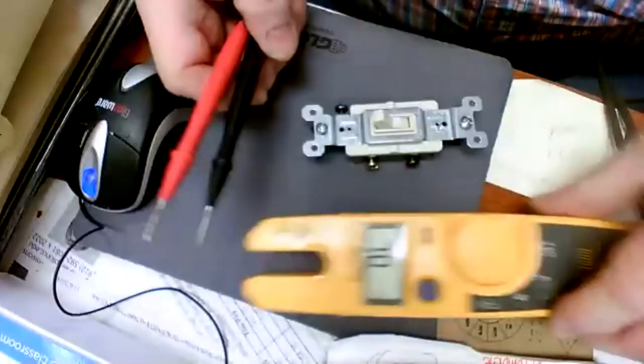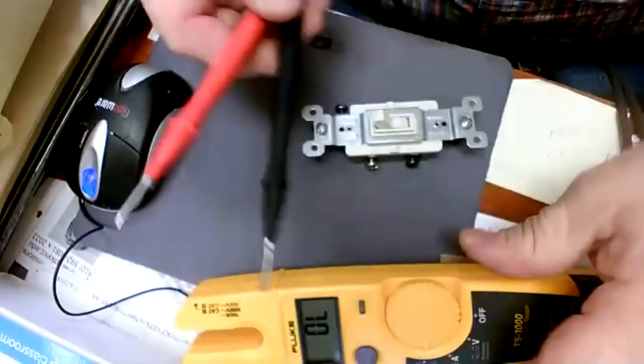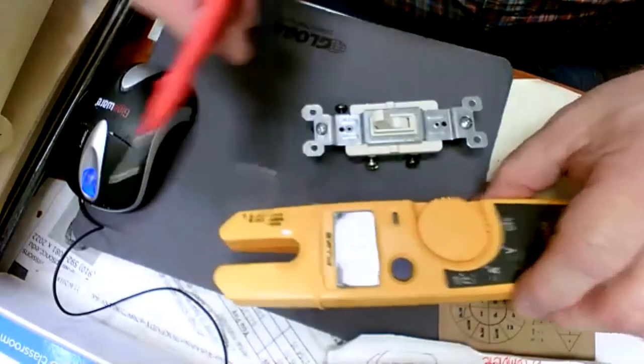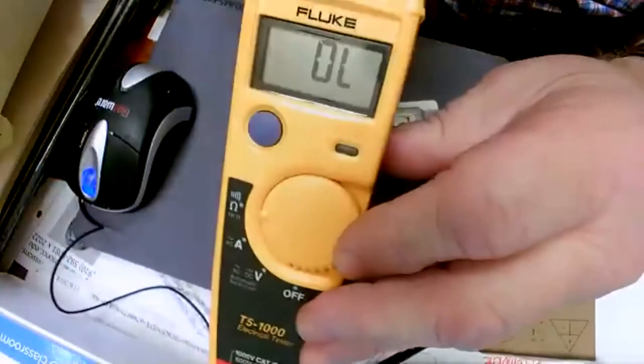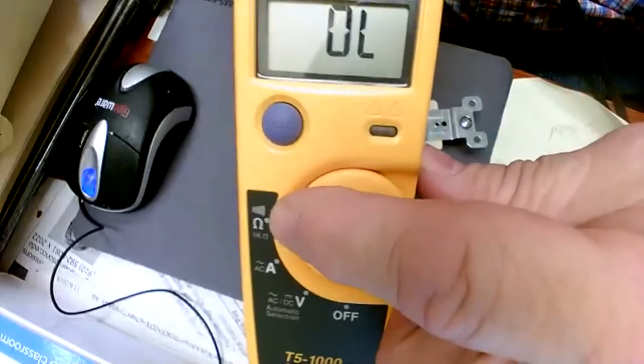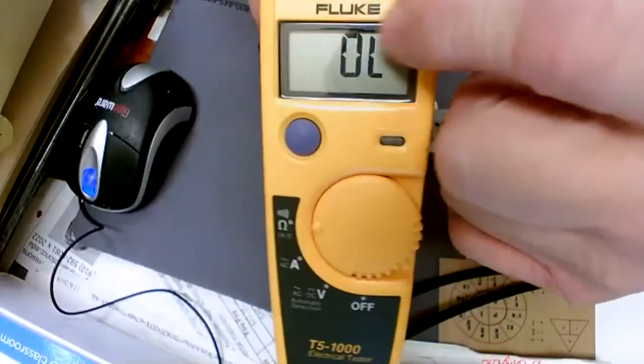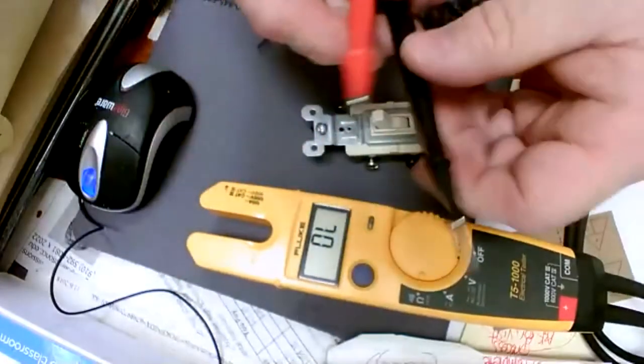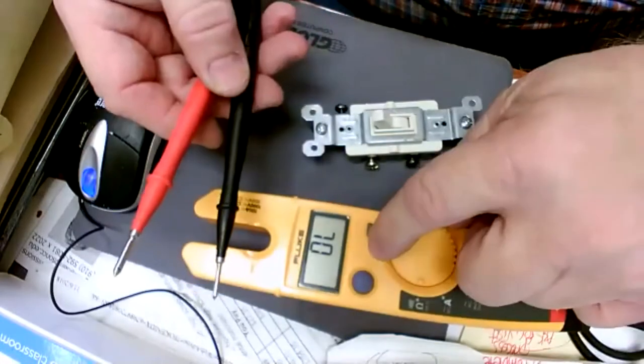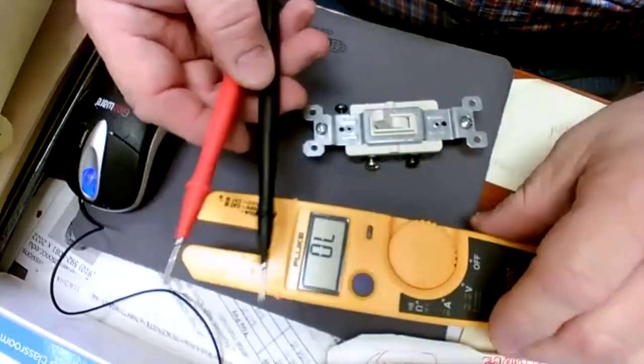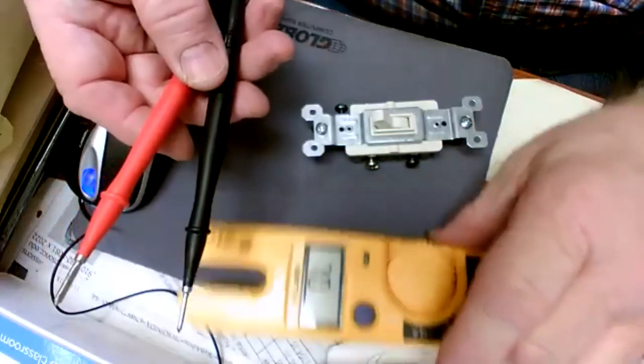Now that's not a single pole switch, that's a three-way. I don't have a single pole in here, but if you were just going to do a basic continuity test with a meter, when the probes are apart, it should say OL, which means over limit. It means it is over the limit of that 1K ohm. It doesn't mean that it's open circuit necessarily, because this meter would not recognize anything above 1,000 ohms. If I measure something 2,000 ohms, it would still say OL.